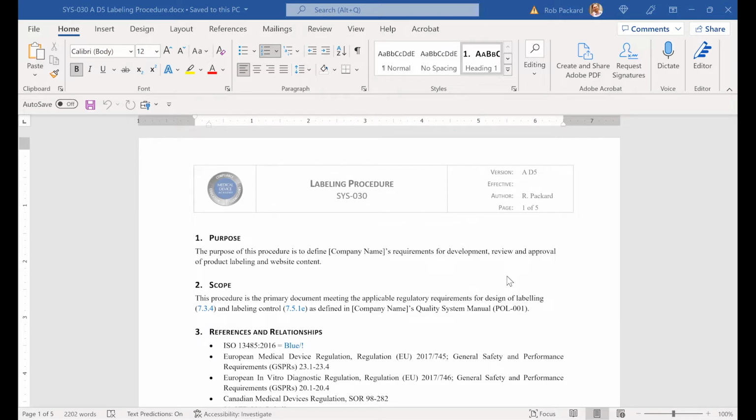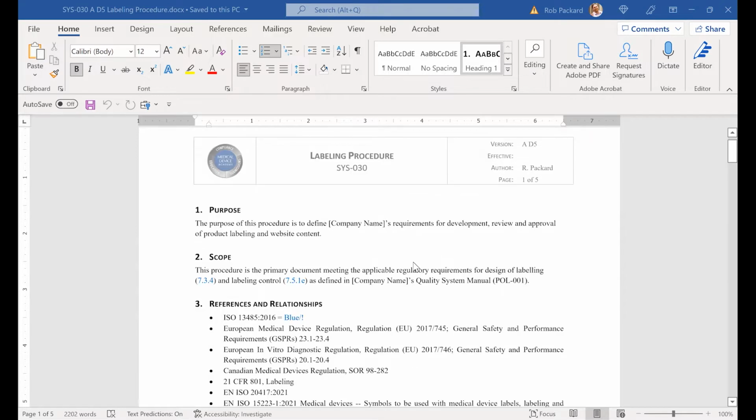One of the things that we've done in our procedures that's new, we've done this for a few months now at least, we started adding color coding and cross-references to requirements in the standards. And this was an idea that Matthew Walker came up with. When we go through certification audits with notified bodies and MDSAP auditors and the FDA, they're often looking for, where can I find this requirement in your procedure? And we found if we put in parentheses, this clause is met by this requirement here, that helps. And having it color coded makes it jump out off the page a little bit.